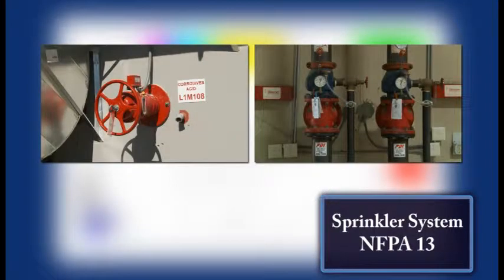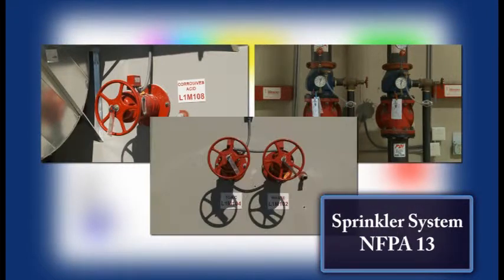Experiences at the Alfa Aesar Bond Street facility have resulted in an internal requirement to be able to control or shut off the fire protection water supply to certain portions of the facility. Accordingly, in addition to the main sprinkler shutoff valve, portions of the fire protection system are arranged to isolate certain areas. All valves are supervised by the fire alarm control panel and are normally open.